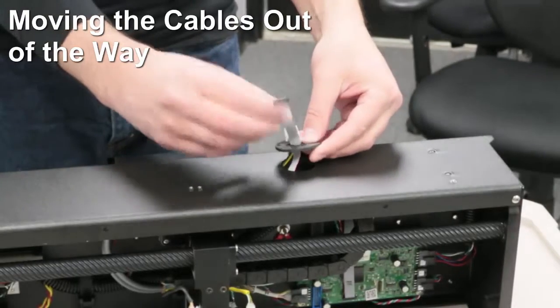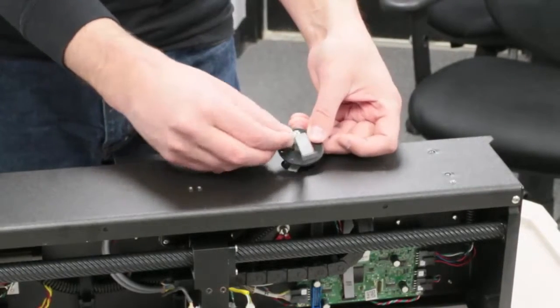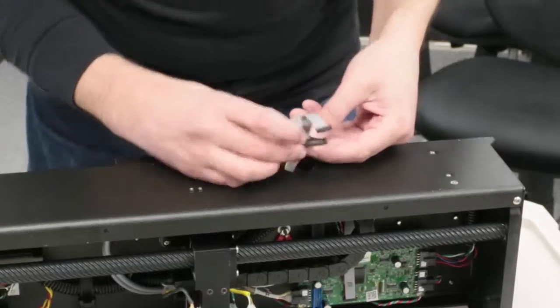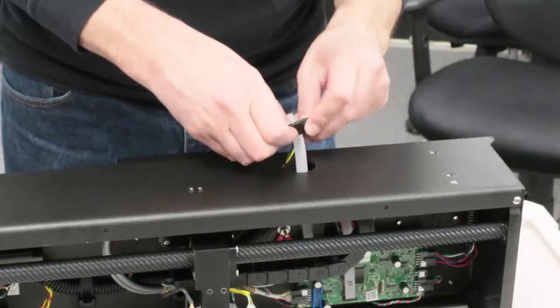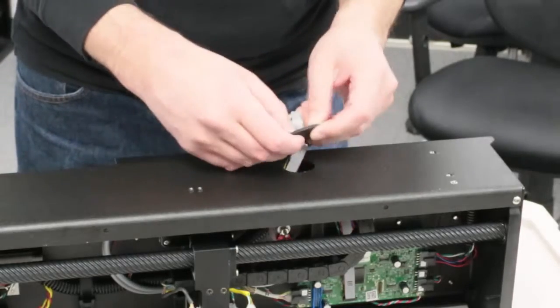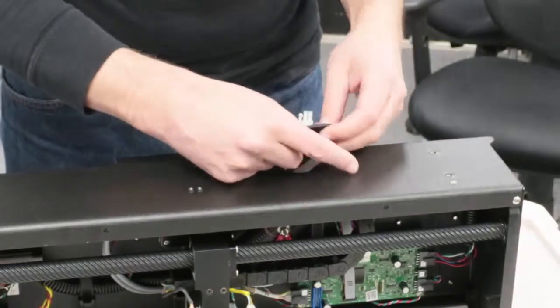Here we see a rubber gasket with a communication cable and a power cable. We'll need to thread the cables through the gasket and push them into the autosampler.